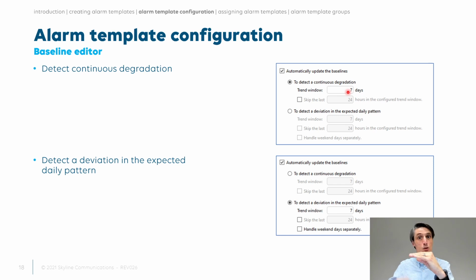I will generate the alarm. So you specify the delta in your alarm threshold. That's the only thing you have to specify, the delta on top of that baseline, and DataMiner will calculate the baseline based on the last 7 days.